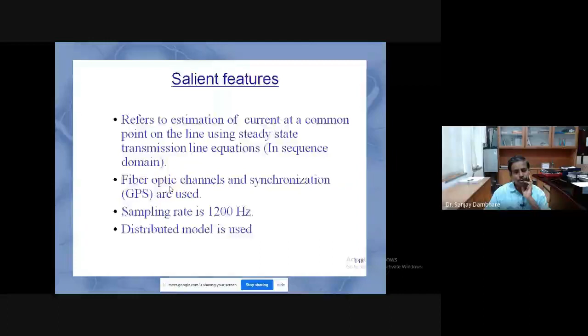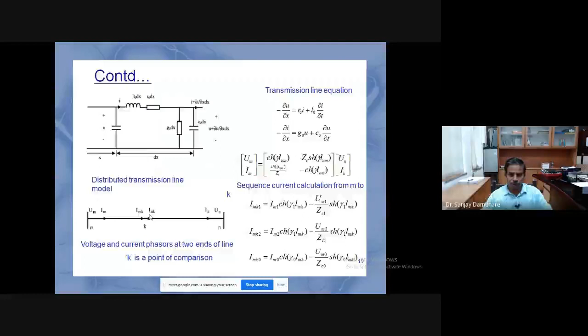What you can do is measure current and voltage at one end and at the second end, and these are time synchronized. So you can take an intermediate point K and compute the current and voltage at that point from this end, and also compute it from the other end. If there is no fault in the system, there's no reason these two computed currents should be different. You can compute this current in the sequence domain - positive, negative and zero sequence - which has advantages in terms of accuracy. All these computations can be done in a processor. These are simple equations taken from the book.